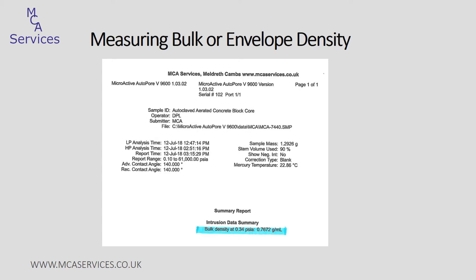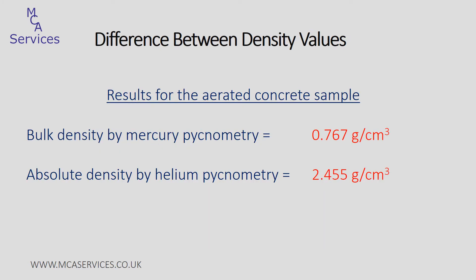Ultimately the Autopore can be used to generate a report showing the bulk density of the sample, and this has been calculated at 0.34 PSIA at a temperature of 22.86 degrees C. We can now look at the difference between the bulk density and the absolute density of this particular sample. There's really quite a big difference and this is entirely due to the volume of porosity within the sample. These are two very different physical properties of the material, and when considering the density of a material — which is quite a critical physical characteristic — both of these values really should be taken into consideration.